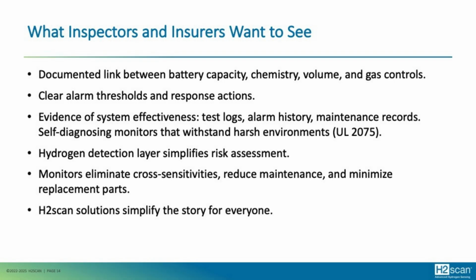And also knowing the maintenance schedule for the sensors and making sure hydrogen monitors have the right replacement parts. So in this case, there are many sensors out there that require replacement parts and calibration. And then there are others like ours that are solid state that require absolutely no calibration and no replacement parts. So choosing the right sensor is very important to make sure that your sensor meets the requirements of your maintenance staff. Many facilities don't have maintenance staff that really know a lot about maintaining sensors, and so having a sensor that maintains itself is very important. And we can basically provide that simplification for your operation.